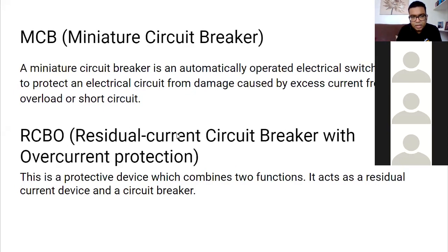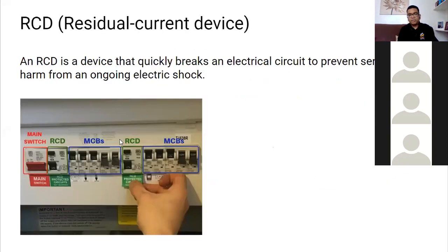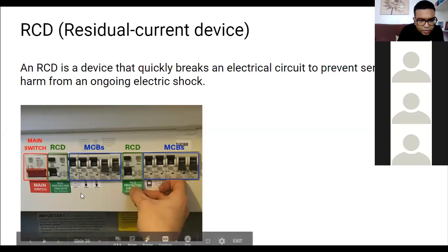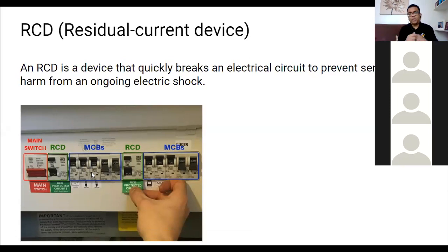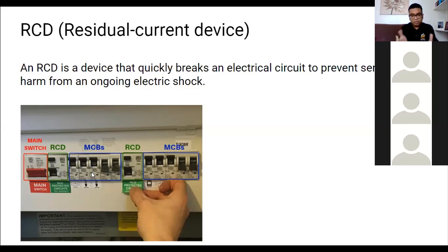An RCD detects earth leakage current. In a circuit, the current going out on the live should equal the current returning on the neutral. If someone touches a fault or there's a short circuit causing leakage to earth, the RCD detects the imbalance and trips to protect against electric shock.